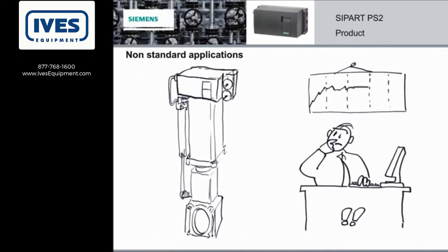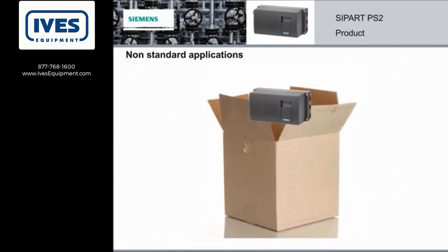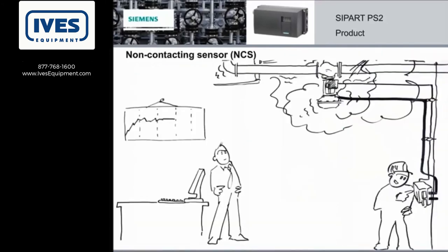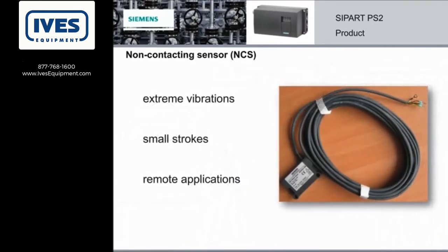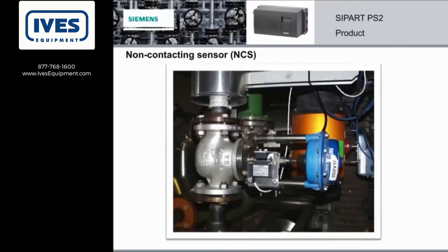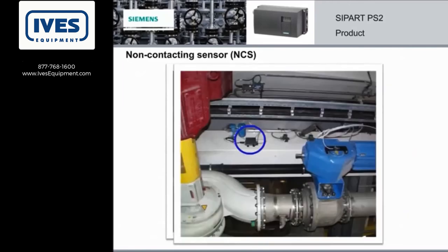For tricky, non-standard applications, the PS2 offers out-of-the-box thinking. The SIPART PS2 also has a non-contacting sensor. This works well in applications with extreme vibration or small strokes — basically wherever remote applications are necessary. The NCS sensor can be mounted with a magnet onto the spindle of linear actuators, or onto the shaft butt of a part-turn actuator. The positioner can then be mounted safely away from your application.